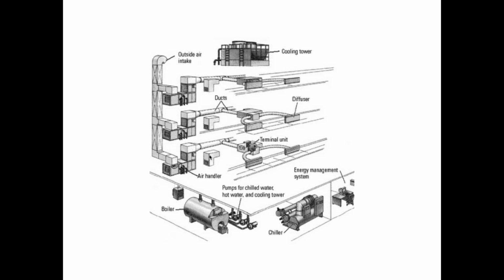And there's a single thermostat on the whole floor, which determines the average temperature on that floor, right? So you get a couple of people complaining it's cold over here, too hot over here, but there's not much you can do about that, because a single thermostat controls the whole floor, or maybe the whole east side of the floor, the whole north side of the floor, or something like that. That's called a constant volume system. The fan runs the same speed all the time.